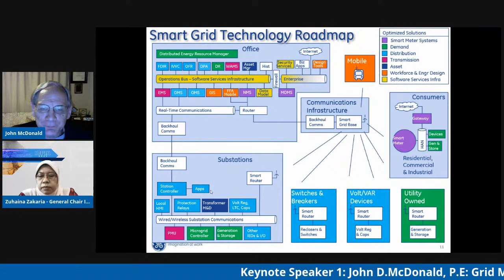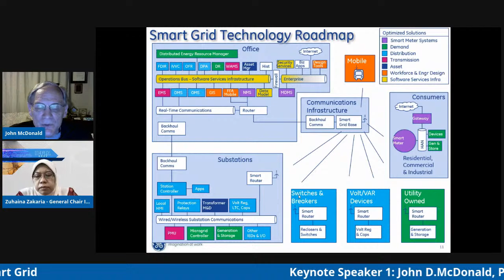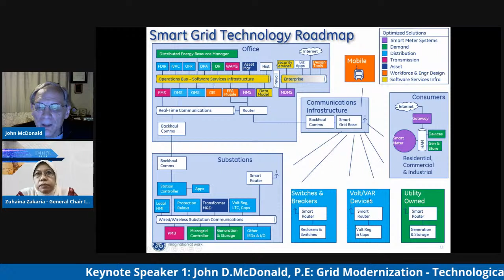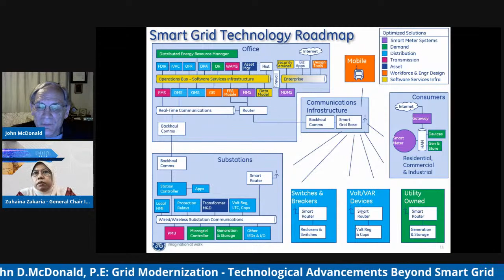Then on the feeders we have switches and breakers, and VoltVAR devices. These switches and breakers support the logic of FDIR: when a fault occurs, we need to detect it, locate it, and isolate it, using these switches and breakers. When we do VoltVAR control, we need capacitor banks and voltage regulator devices on the feeders, which are these VoltVAR devices.